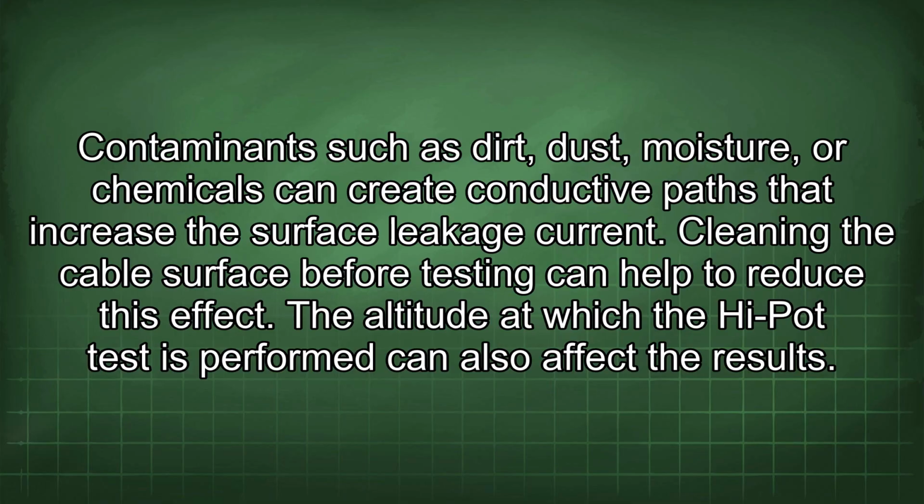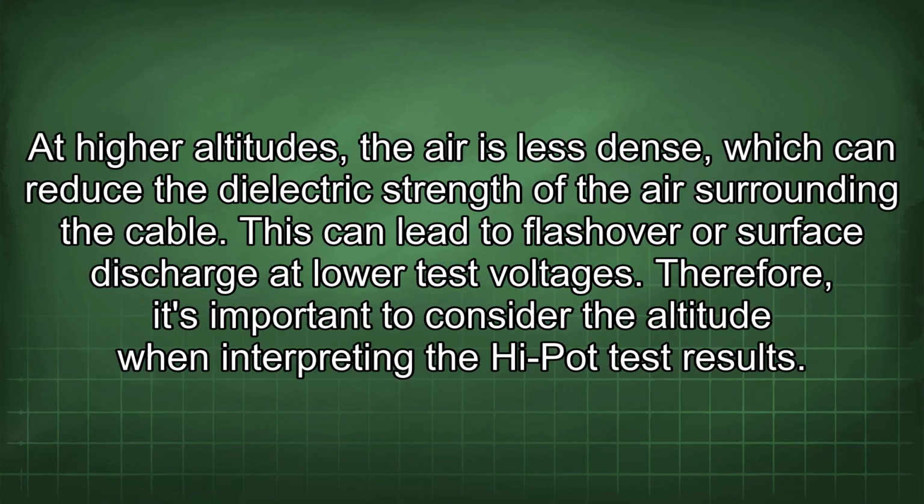The altitude at which the high-pot test is performed can also affect the results. At higher altitudes, the air is less dense, which can reduce the dielectric strength of the air surrounding the cable. This can lead to flashover or surface discharge at low test voltages. Therefore, it's important to consider the altitude when interpreting the high-pot test results.